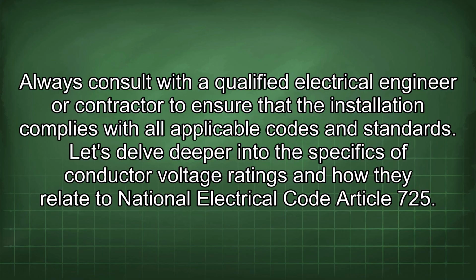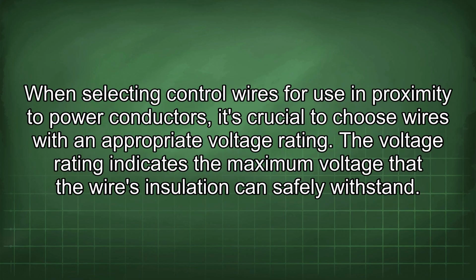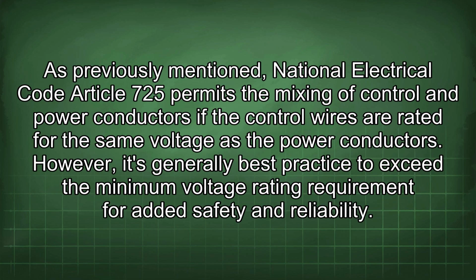Let's delve deeper into the specifics of conductor voltage ratings and how they relate to National Electrical Code Article 725. When selecting control wires for use in proximity to power conductors, it's crucial to choose wires with an appropriate voltage rating. The voltage rating indicates the maximum voltage that the wire's insulation can safely withstand. As previously mentioned, Article 725 permits the mixing of control and power conductors if the control wires are rated for the same voltage as the power conductors. However, it's generally best practice to exceed the minimum voltage rating requirement for added safety and reliability.